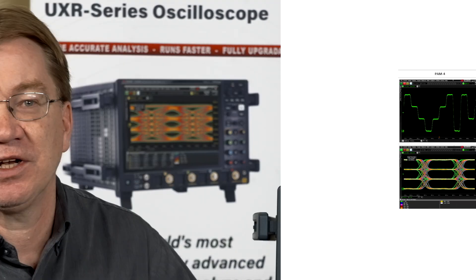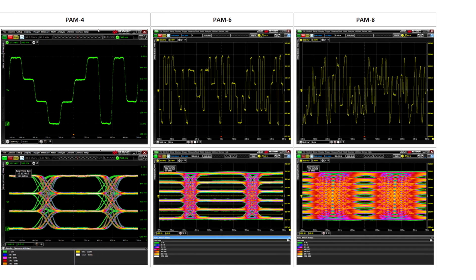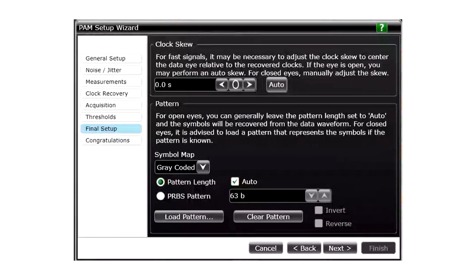The Keysight PAM-N analysis software extends these ease-of-use advantages of the Infiniium oscilloscope to the analysis of PAM-3, PAM-4, PAM-6, and PAM-8 signals. A wizard walks you quickly through the steps required for the setup of measurements of PAM-encoded signals, to select the methods for clock recovery, and then the measurements you wish to have performed on your PAM signal.